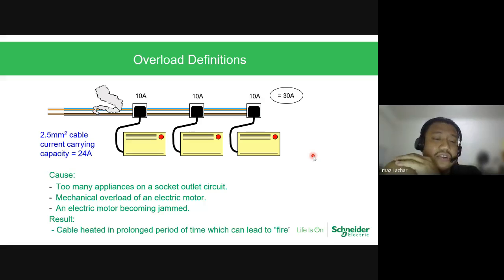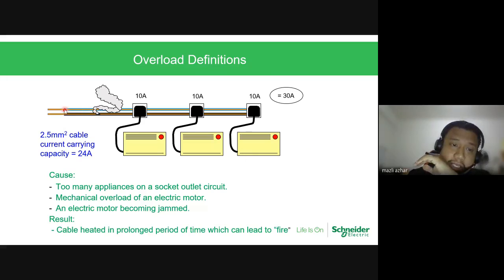It may also occur because of mechanical overload of a motor, or the motor jamming. So what is the result? The cable is heated over a prolonged period of time, which can lead to fire. So if you put an MCB here, it will detect an overload and trip the whole circuit, to ensure that there is no effect on the loads or on the cable itself.